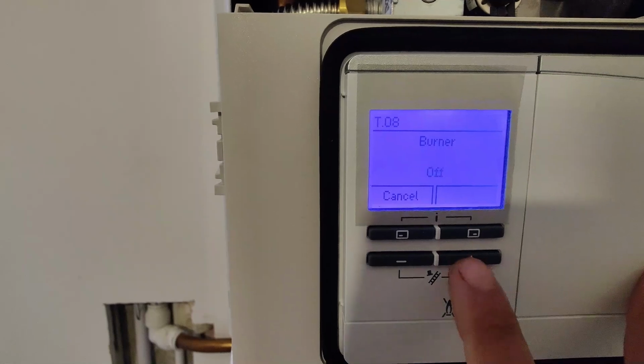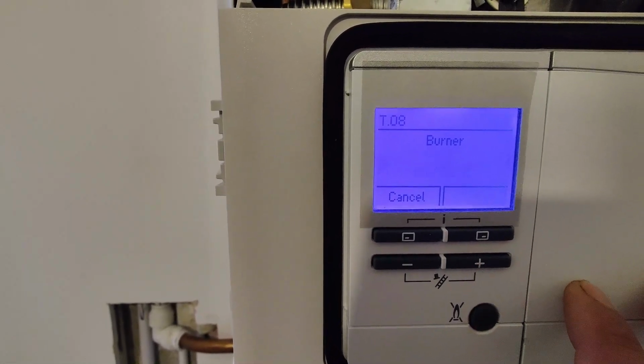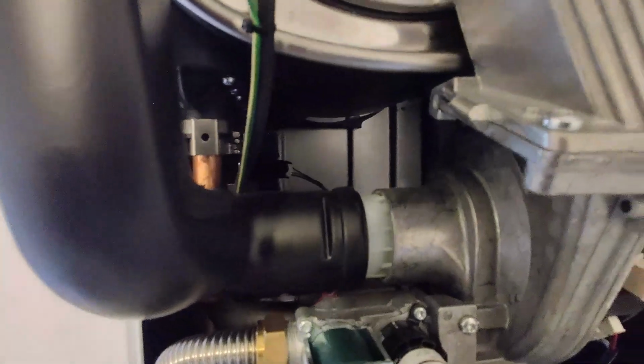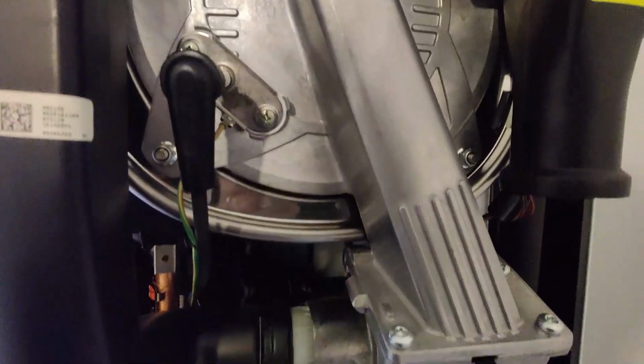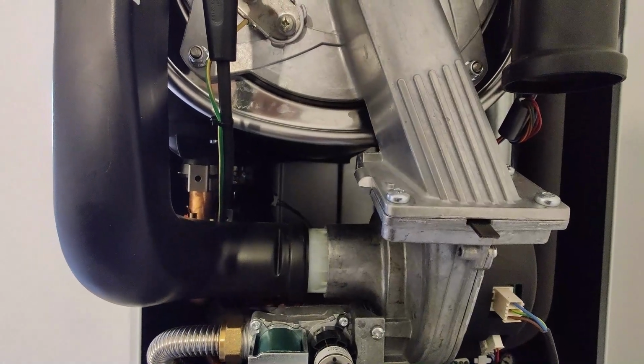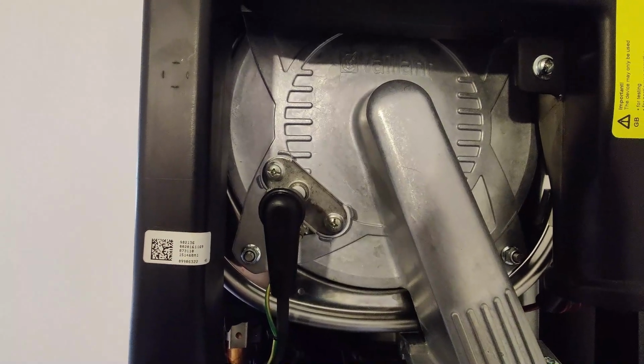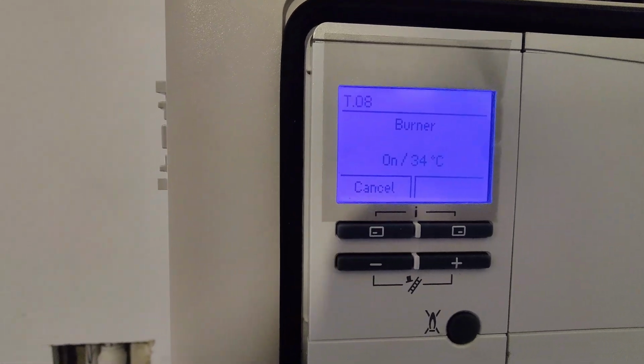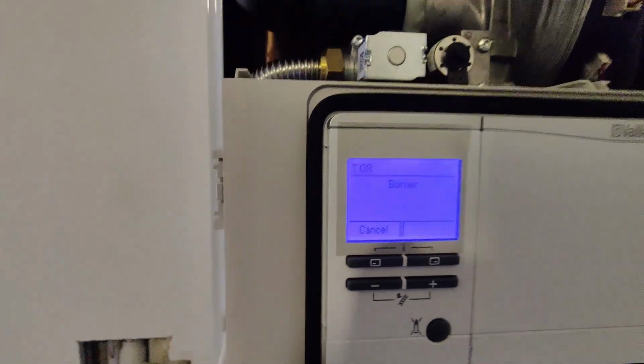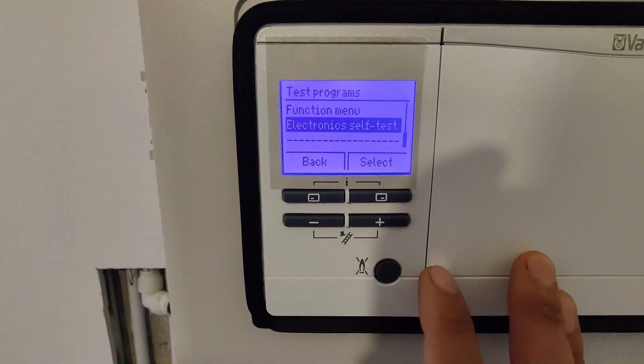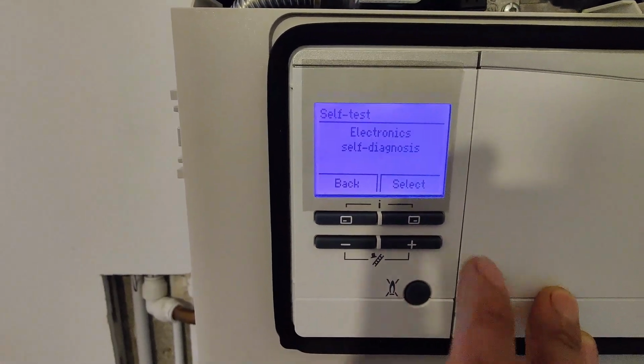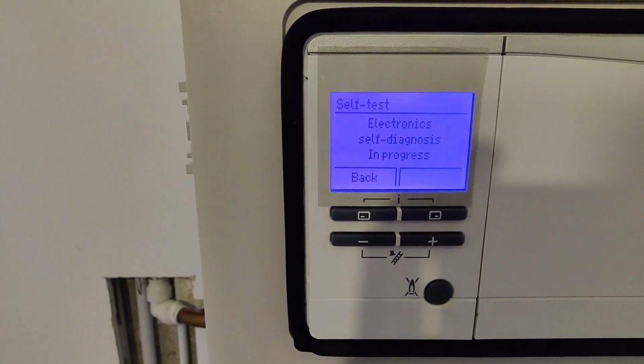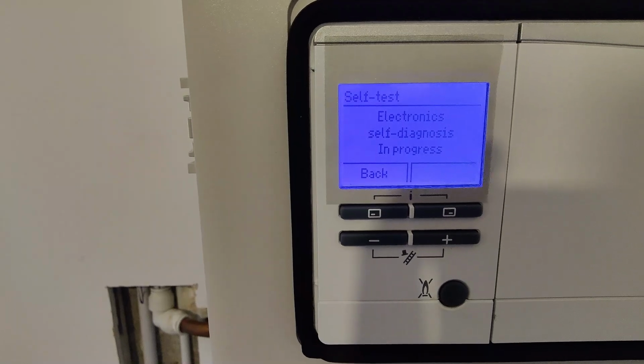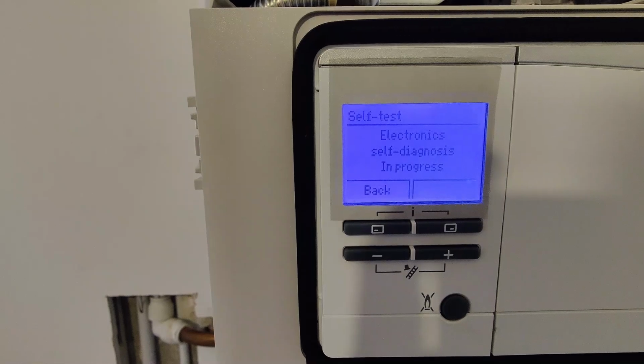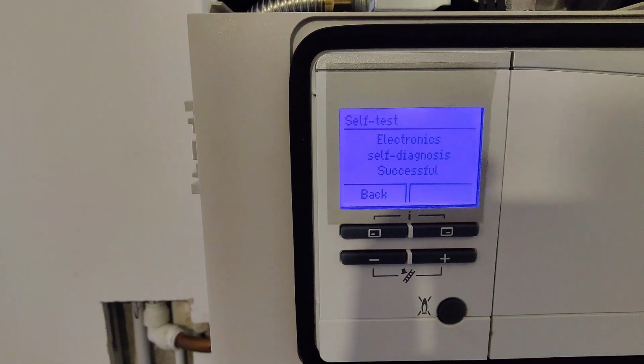And you can actually turn the burner on. So when you select it, it's off and it's at 22 degrees. Let's turn it on. That's the fan. Ignition, and it's moved from 22 to, as you can see, it's rising in temperature. So it also confirms that your burner is on. You can also do the electronic self-test on it as well if we activate that. That's in progress. And that was successful.